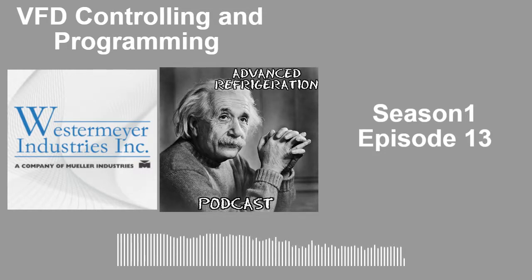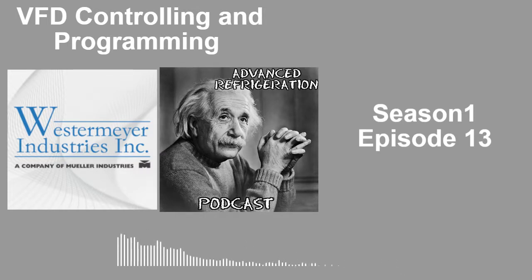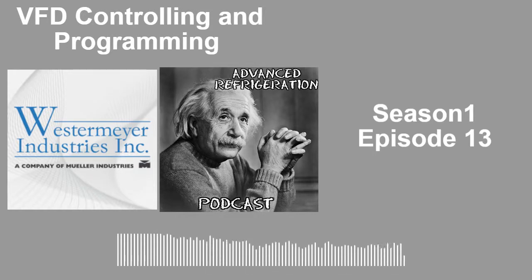I mean, most of the stuff I see with smart drives is Danfoss and some NIDEC stuff, but the Danfosses work extremely well. Probably one of the best condenser drives you can get. Very easy to set up. The way they're doing it is they're taking two analog signals. You get your outside air temp sensor, which you'll be using to figure out TD, and they're going to be using your drop leg pressure or your discharge pressure, depending on how the customer has it set up.